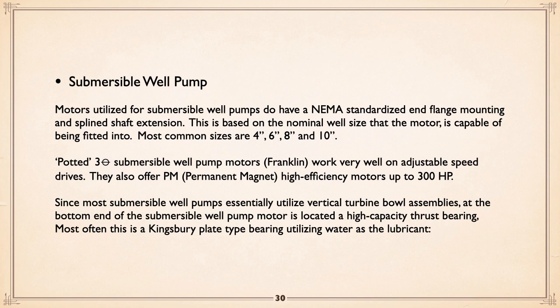Submersible well pump motors. There is a standardized design on the end of them, NEMA standard, and so motors are interchangeable, manufacturer to manufacturer, assuming they have either 4, 6, 8, or 10-inch bases. And what that means is a 4-inch motor will fit. It's a bit smaller than 4 inches. It's designed to fit within a 4-inch inside diameter well, or 6 or 8 or 10.